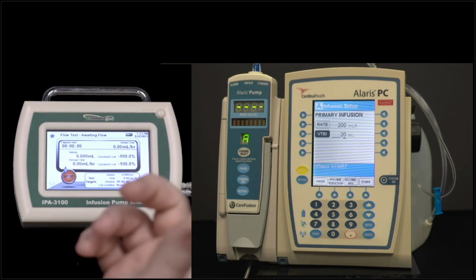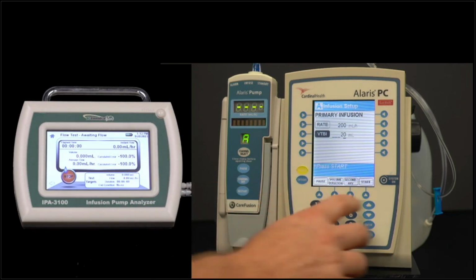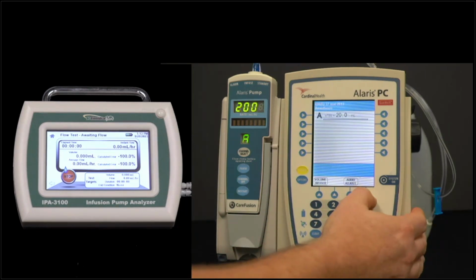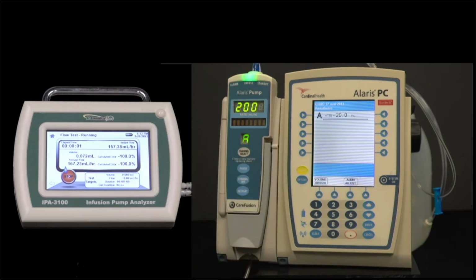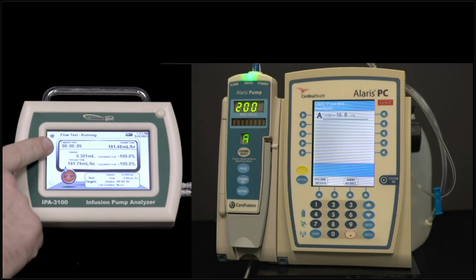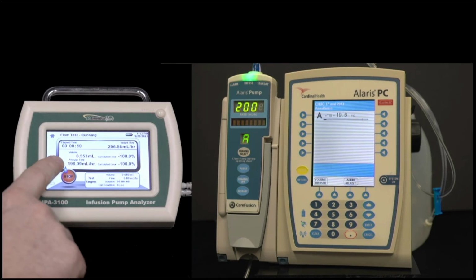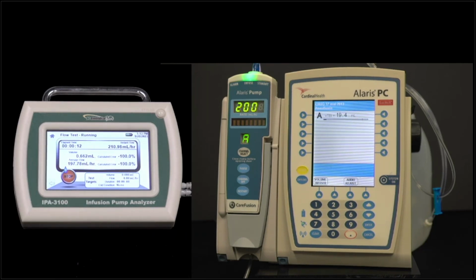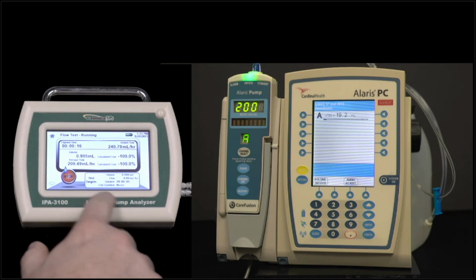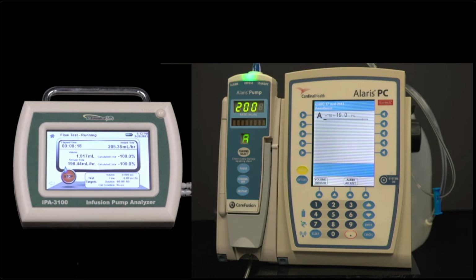I don't have to worry, it's waiting for the flow. So as soon as the flow begins, then it's going to start measuring. So I'm going to press start on my pump, and here we go. We've got measurements, it's going. We've got elapsed time, we've got instantaneous flow, and we've got our average flow and average volume, the total volume delivered.